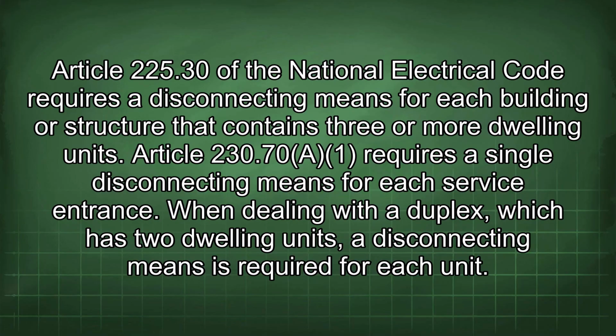Article 225.30 of the National Electrical Code requires a disconnecting means for each building or structure that contains 3 or more dwelling units. Article 230.70 requires a single disconnecting means for each service entrance. When dealing with a duplex, which has 2 dwelling units, a disconnecting means is required for each unit.